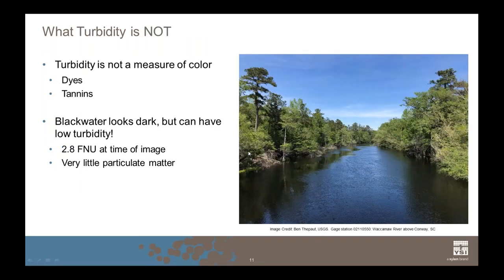What is turbidity not? Turbidity is not a measure of the color of water. Colors can be introduced by dye studies or from tannins leaching into the water as surrounding vegetation decays. This image shows a Blackwater River in South Carolina — the river is literally black due to dissolved materials, but there's very little particulate matter. At the time this image was taken, turbidity was only 2.8 FNU, which is very low.